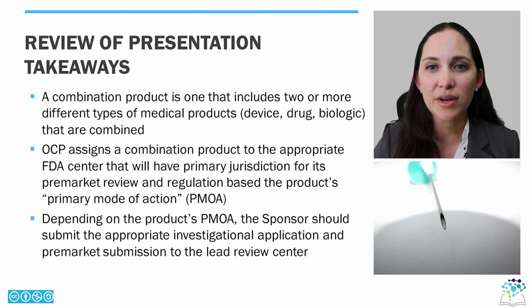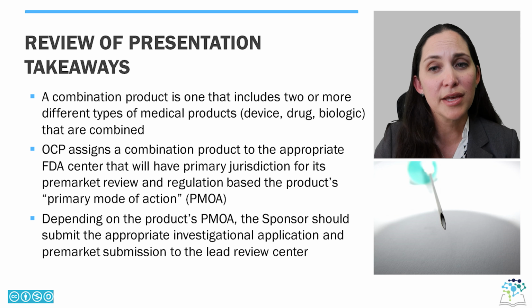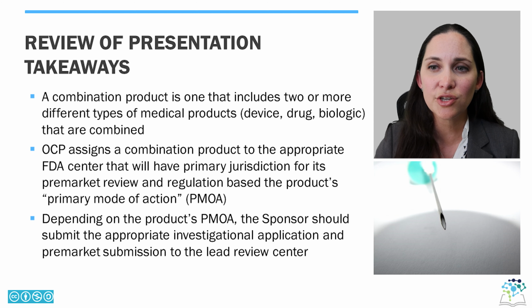All right, let's review our key takeaways from today. First, a combination product is one that includes two or more different types of medical products, either a device, a drug, or biologic, that are combined. The Office of Combination Products, or OCP, assigns a combination product to the appropriate FDA center that will have primary jurisdiction for its premarket review and regulation based on the product's PMOA, or primary mode of action. Finally, depending on the product's PMOA, the sponsor should submit the appropriate investigational application and premarket submission to the lead review center.